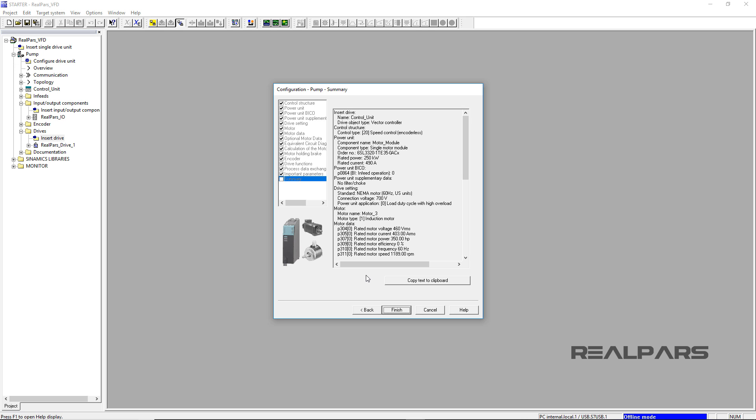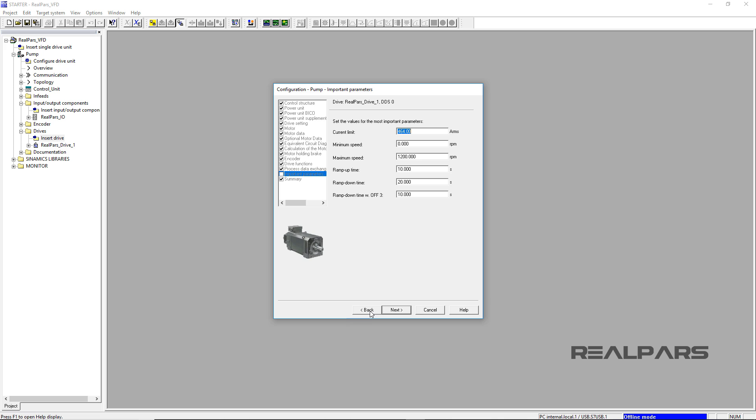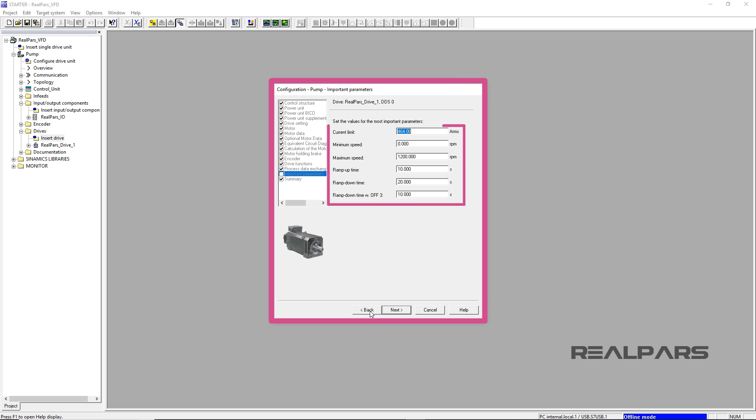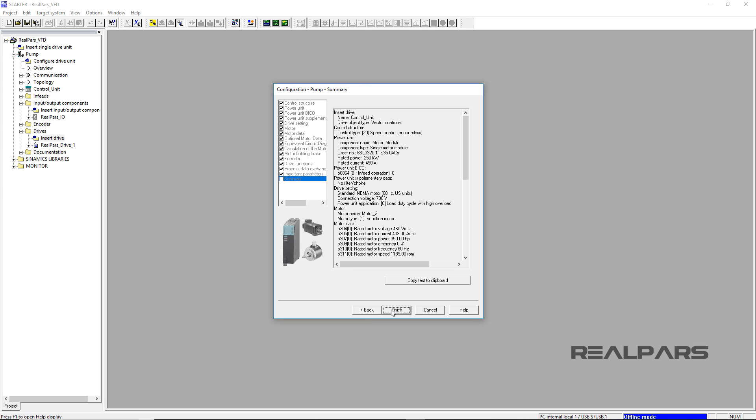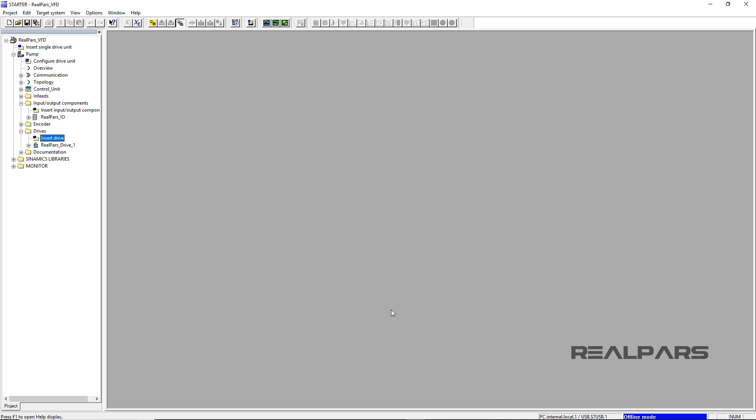In the previous part, I left off right after completing the motor and its nameplate data configuration. Let's pick up from the last step of the motor configuration where we had configured the important parameters of the motor. In the important parameters display, I set some of the important parameters according to the motor's data sheet. I continued by selecting the Next button and the Pump Configuration Summary display appeared. I selected the Finish button to continue.